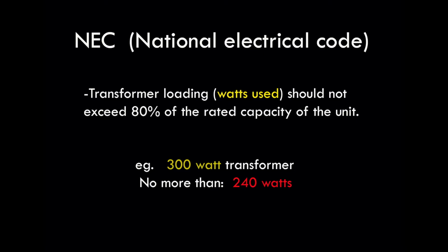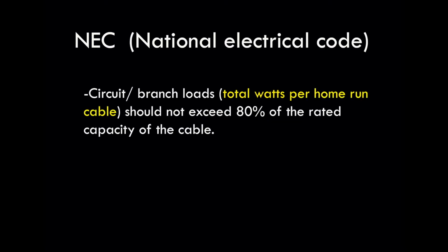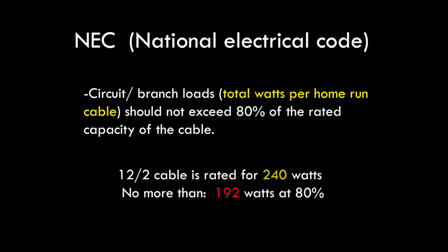Exceeding these limits puts your transformer in a dangerous situation. The National Electrical Code further states that circuit and branch loads, which is the total watts per home run cable, should not exceed 80% of the rated capacity of the cable. The most common type of landscape cable is 12-2, and it's rated for 240 watts worth of load. Now, you should never use more than 80%, which is 192 watts. If you begin to exceed that, your wire will get very hot and potentially could melt.